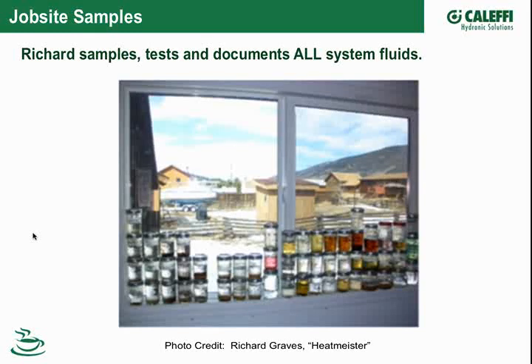It's oxygen, heat, and failure to maintain the pH and the corrosion inhibitors in their acceptable ranges. The discoloration can be caused by thermal oxidative degradation and corrosion. And so really, it's a great slide, because a visual inspection of your fluid, you may not be able to know exactly what's wrong with your fluid, but if it looks funny, it looks bad, the odds are there definitely is one or more fluid parameters that are out of range. And so it's a simple but powerful test you can do for your fluid.